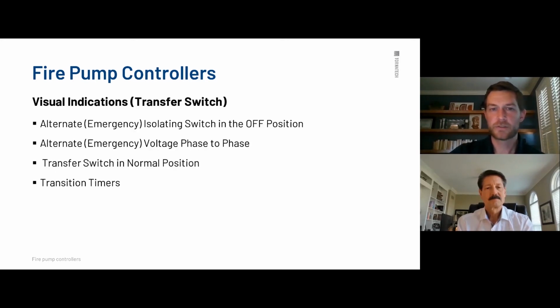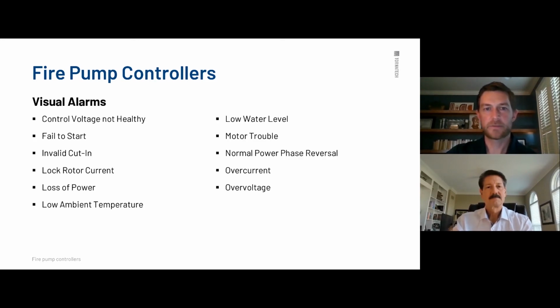So if you have a transfer switch, we also have to have visual indications for the position of the isolation switch, the voltages, which I showed you on that one as well, where it's right below the normal power. That's where you're going to see the emergency power voltages, and then whether or not the transfer switch is in normal position, which is where we indicate with that triangle. That's the indicator if it's on normal power or on alternate power. And then also transition timers. Some of the visual alarms, there are several of them for that as well.